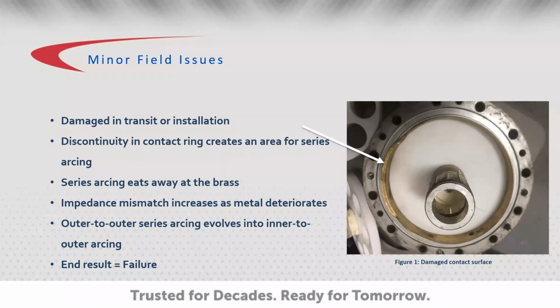This could evolve into inner to outer arcing, eventually leading to component failure, and the transmitter would see this and not let you turn itself on. And at that point, you're going to see melting of the insulator, as well as, if this was in the vertical section, any of that would then just fall down due to gravity.